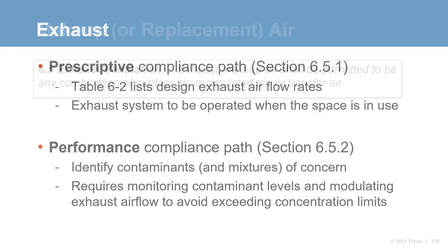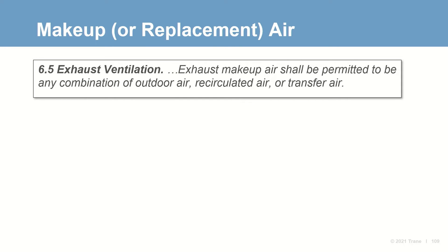Regardless of which compliance path is used, this section clarifies that make-up air — that's the air that replaces any air being exhausted — can be comprised of outdoor air, recirculated air, or air transferred from another ventilation zone. This provides flexibility for the designer.